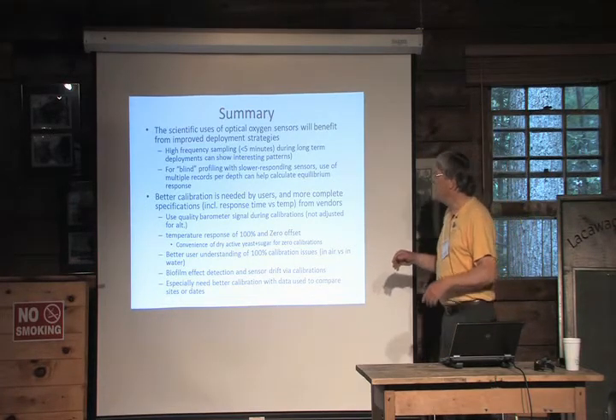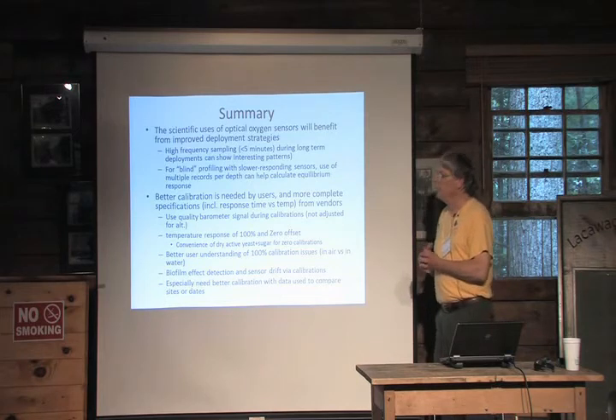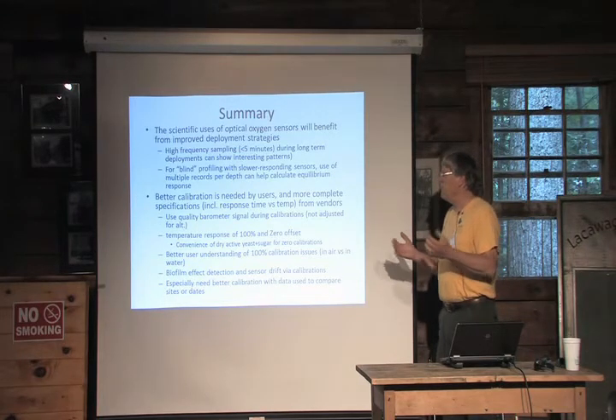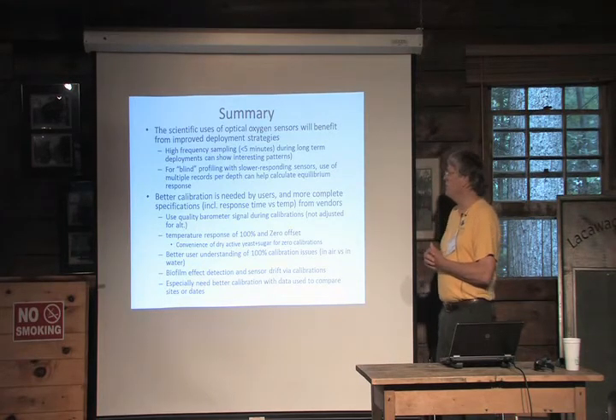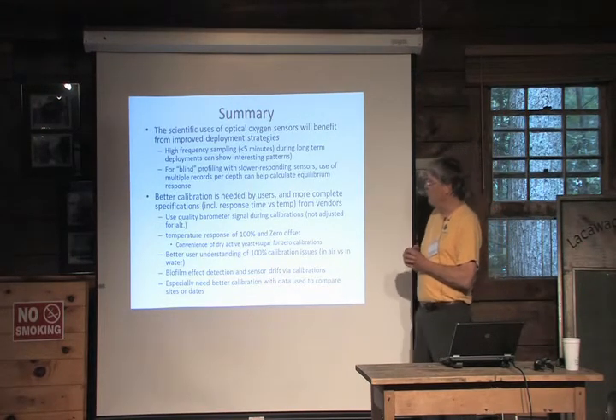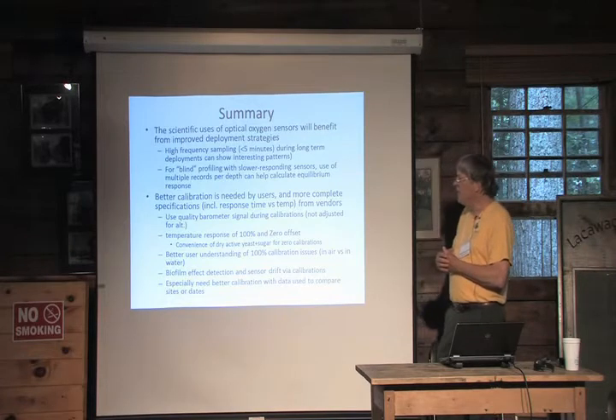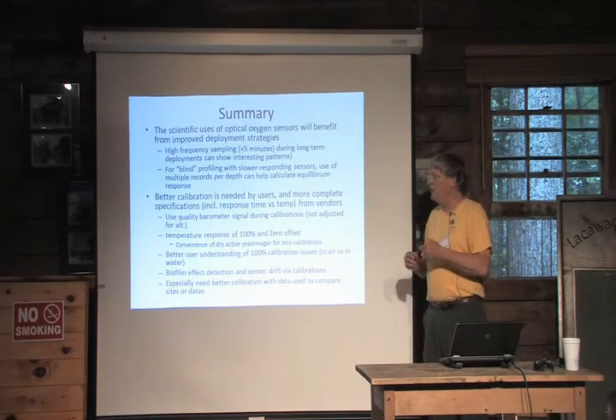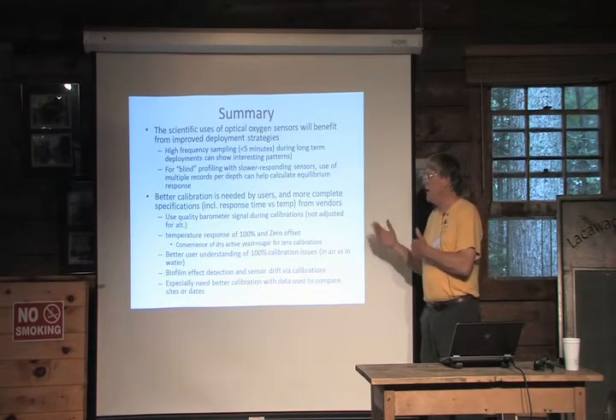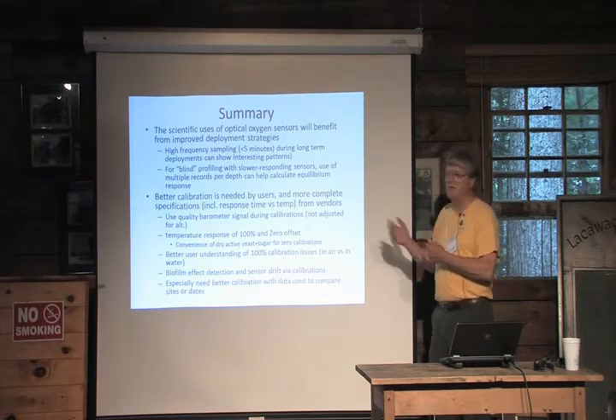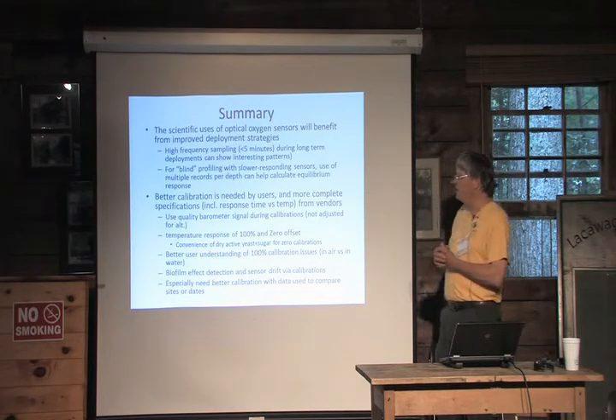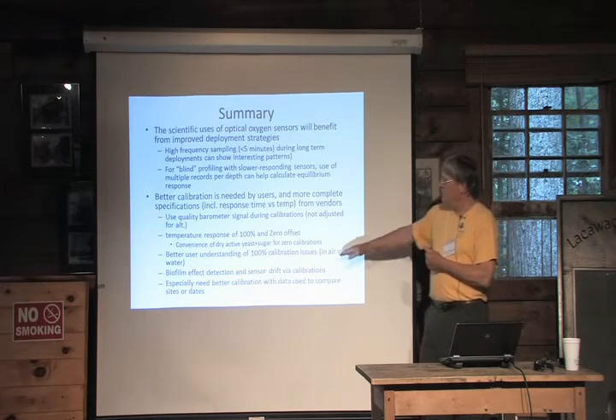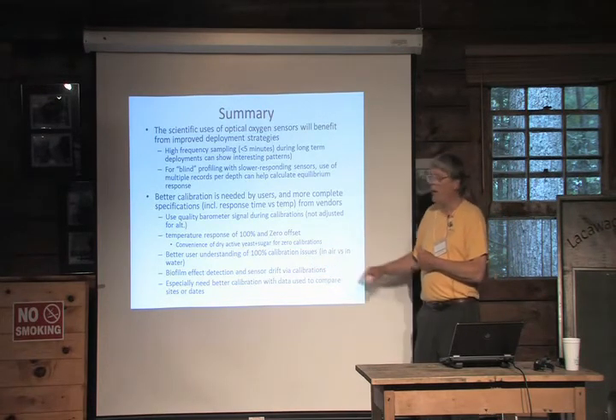Better calibration is needed by users. I think many people may just not calibrate their instruments for lack of time or not know how to do it well, but you do need a good quality barometer signal to do it well. You should do an equilibrium and zero offset value. Yeast is a convenient way to get the zero offset now, instead of using sodium sulfite. And you have to think about whether you want to do it in air or water because there are trade-offs to both.